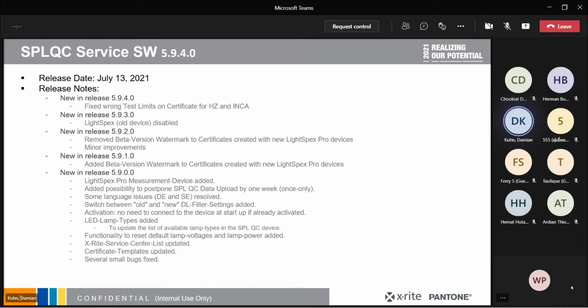5.9.0. The other newer versions were just minor updates where we added watermarks for beta testing. Then, once we were satisfied, we made a couple of improvements and removed those watermarks. At one step, we also removed support of the old Lightspex instrument, and about a week ago we did another new release that has a bug fix on some of the test limits on the certificate issued to customers for Horizon and Incandescent A light sources.